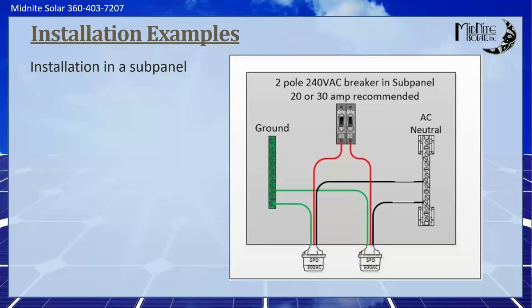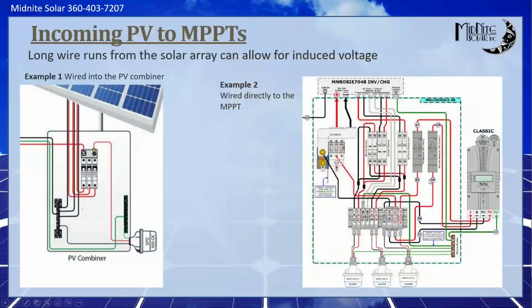So in this case, you use a couple SPDs, use the white heat shrink that we include on the blacks and put them under the neutral, the greens to the ground, and then the two reds to the two legs of your subpanel if it's 240. If it's 120, then you only use one SPD: white to neutral, green to ground, and your red wire to your hot leg in your subpanel. But make sure we're protecting that subpanel.